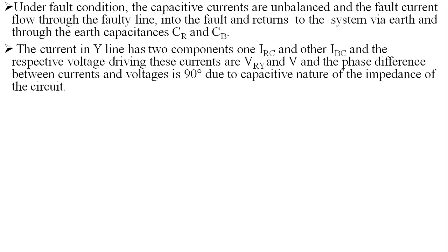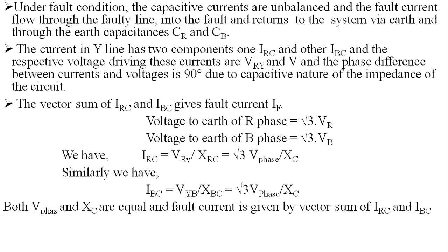current IF. The voltage to earth of the R phase will be root 3 times VR. For the B phase, it will be root 3 times VB, and IRC will be equal to VRY by XRC, and that will be equal to root 3 times V phase by XC. Similarly, we have IBC equal to VYB by XBC, and that will be equal to root 3 times V phase by XC. Both XRC and XBC are equal, and the fault current is given by the vector sum of IRC and IBC.